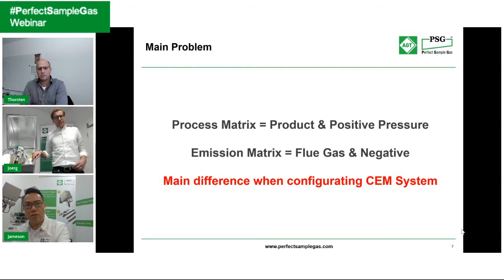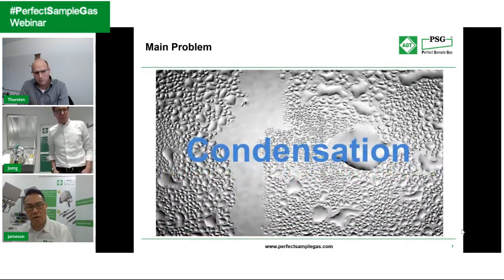So to put this in a nutshell, I try to say the word condensation. Condensation is the biggest mistake if it is not taken into consideration right from the beginning. Condensation happens in flue gas systems because, remember, it is negative pressure. Once you create a positive pressure, you are changing the dew point. Once you change the dew point, the water in the sample will start to condense, and that is where it reacts with some particles and some acid to become corrosion, and it all affects your gas analyzer.